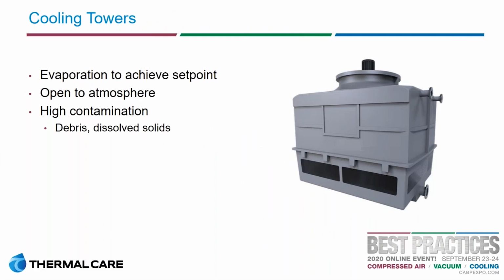Next, we'll talk about our cooling towers. A cooling tower uses evaporation. With a cooling tower, evaporation is a very effective means of rejecting heat. It does a great job of absorbing energy. What happens is we're going to spray water, and I'll show you a diagram of this in a second, and we'll use air to cause partial evaporation. So what's left is a cooler water. Part of the problem with the cooling tower is that it is open to the atmosphere, and I've heard it referred to as a big air scrubber. So anything that's in the air, leaves, dirt, dust, cottonwood, anything like that, is going to be pulled in and can enter into your processed water.